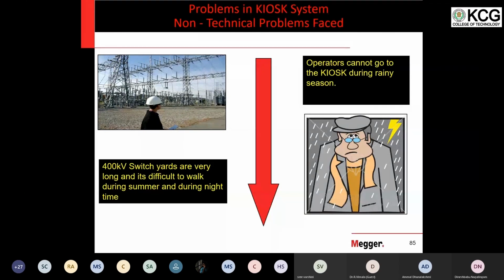But SCADA has failed. Computer has failed. Now what? Your system is still running perfectly because the relay has not failed. Only if the relay fails, the system is not permitted to operate because that is the main protection. But if SCADA fails, SCADA is only control and monitoring. It is not as important as the relay. So when the relay is in service, we still continue to run the system. But what will happen? The operator has to run from kiosk to kiosk. So what I showed here is only one kiosk. You may have several kiosks in a bigger substation. So by the time he completes one circle, 1 hour will be over. So from morning to evening, he will be running from kiosk to kiosk to note down the hourly reading. The second example is during night time and rainy seasons: how will he manage this situation?